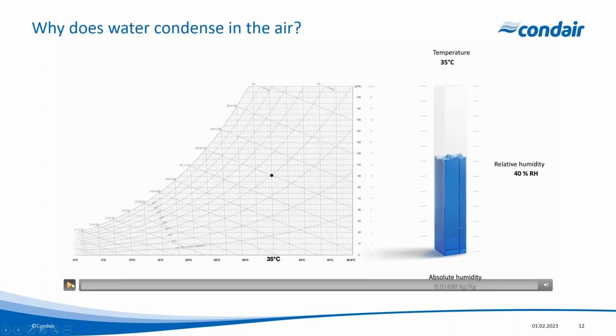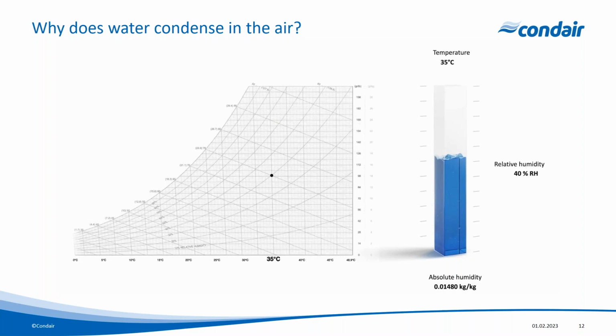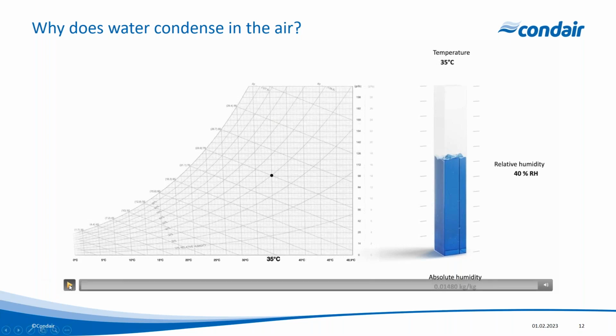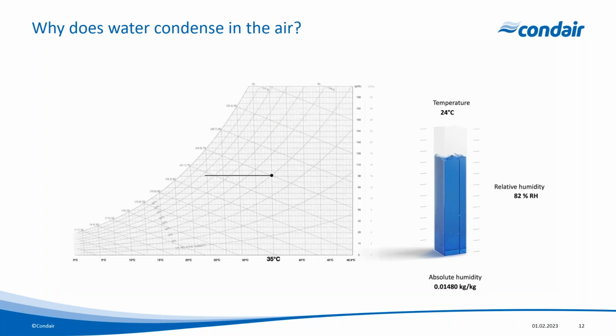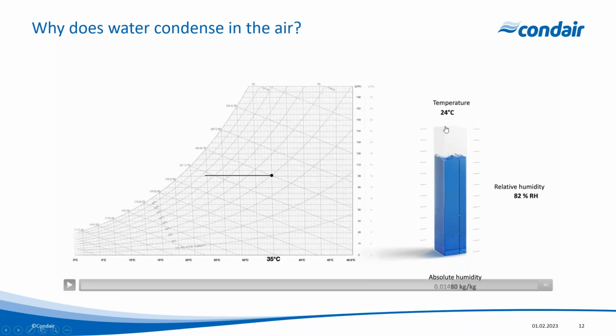And that's fine. But what happens when we cool the air is that air contracts, but the amount of moisture in the air stays the same. So if we contract this air, you can see now that the temperature has dropped. So we've cooled the air down to 24 degrees C, but the amount of moisture in the air has stayed the same. So our relative humidity, so the percentage saturation, has increased, but again, my absolute humidity has remained the same. And this is reflected in the psychrometric chart.